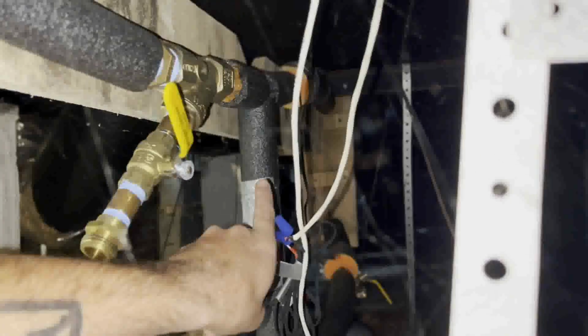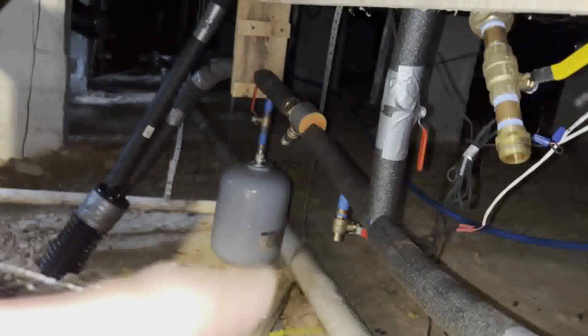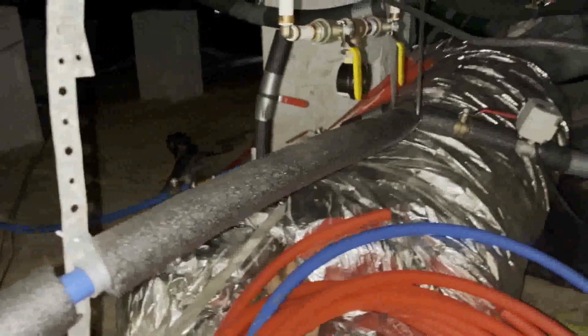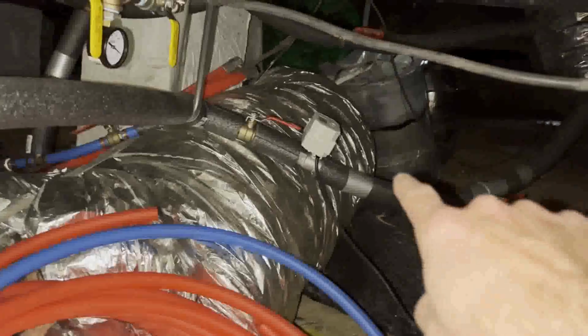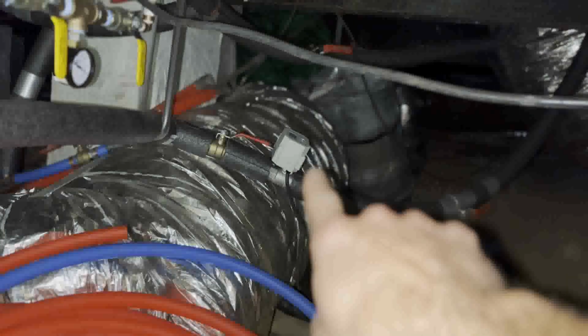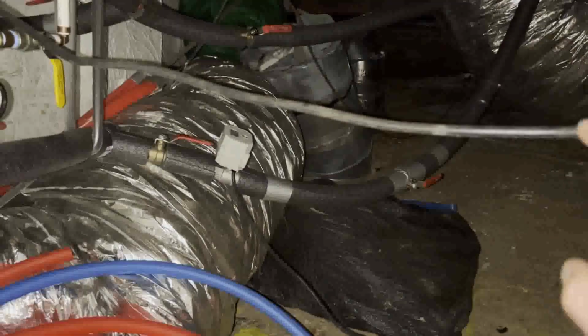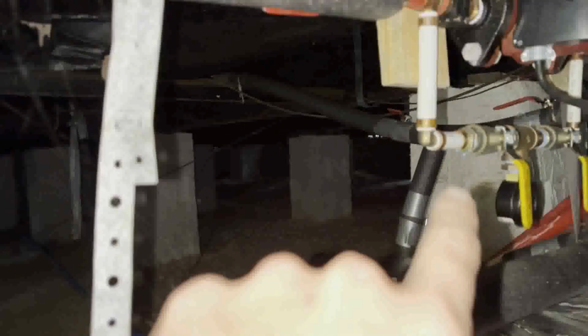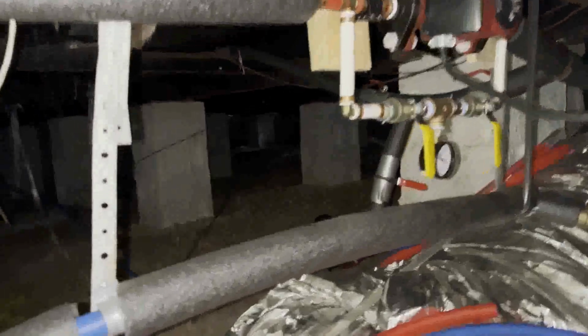So the supply is coming in up top, coming this way. This is a low loss header. That is open. That decouples, that separates the primary loop, which ultimately comes up that pipe, around and down like that. So that's the loop right there. This is the secondary loop, pulling from this side here, around, going to some tees, valves. There are other components here: strainers, expansion tank, check valves, a few of those things. I can talk more about that. This is another one of those actuators. When it loses power, it opens. So that line goes to a heating coil that's in the return plenum of the house, and that's the return line. That line there in the back, that's the supply that goes over to the water heater with a sidearm heat exchanger.